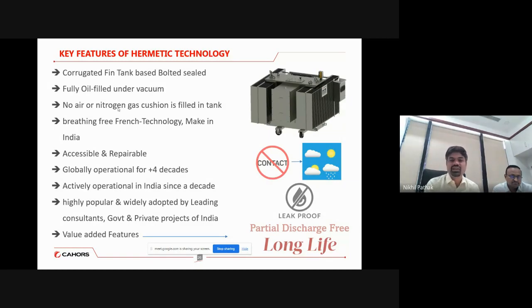First of all, it is a compact transformer. It has a low footprint. So regarding the carbon footprint, we are talking about green energy, sustainable energy, reduced footprint, compactness, optimization. All these concepts are delivered in the hermetically sealed design. Secondly, oxidation is avoided. Third, it is leak proof. So it is partial discharge free, and hence it gives a long life approach. These are the key features of the hermetically sealed transformers.